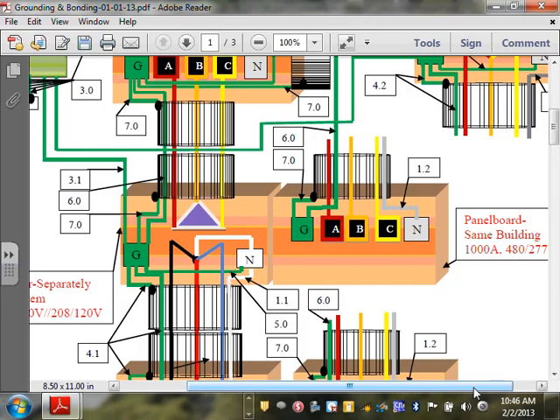Or if you're using PVC, let's just say we're using PVC, then you have to pull an equipment grounding conductor with it. Also, for 1000 amp switchgear, I will probably pull an equipment grounding conductor just for safety, just to make it safer. But remember, I'm not paying for it, and you guys are bidding it and installing it. If you use conduit, are you required to put a grounding bushing on either end then?